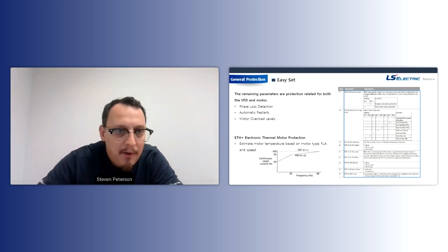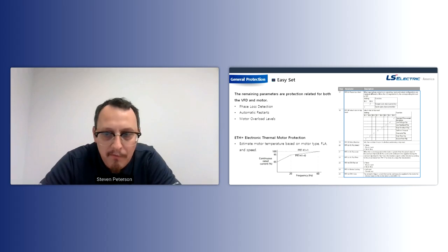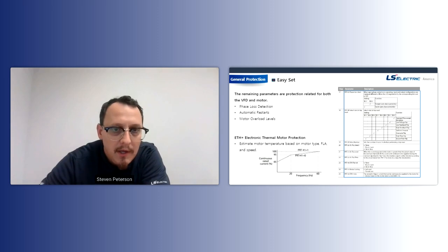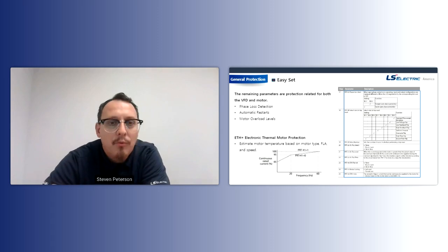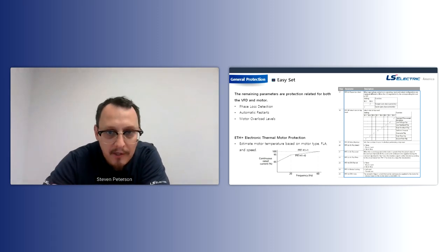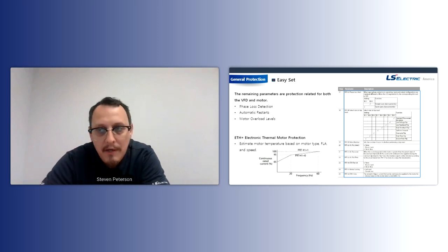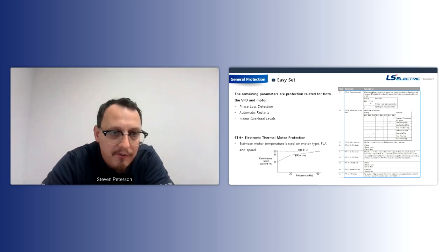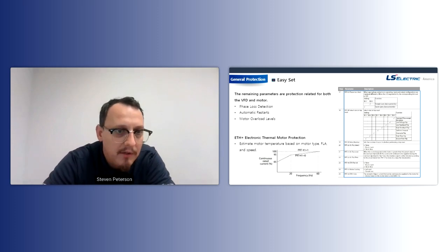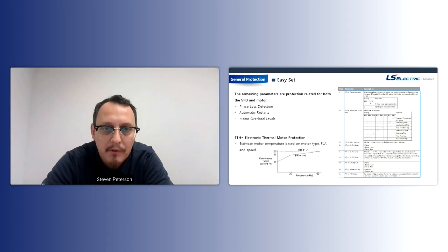So the last part of the easy set I'm going to mention, before we switch gears into PID, which I think you guys will find interesting, is just some remaining parameters related to protection. Okay, so some of these are drive protection parameters, some of them are protection parameters for the motor. So the key ones we're going to talk about are phase loss detection, automatic resets, and then also the motor overload levels.